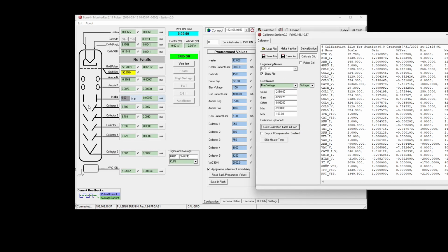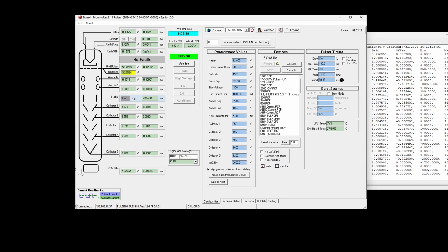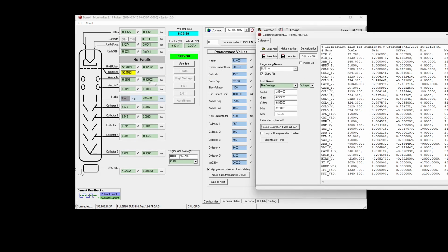Essentially what we're doing, especially for the bias, is we're assuming that we cannot reach 0. We cannot turn off and ground the grid and take an offset. So we have to do this with both points powered up. And at a low end, the lowest end we can get, we're going to say 100 volts negative. We're going to adjust offset, and 1500 volts negative will be our gain adjustment.